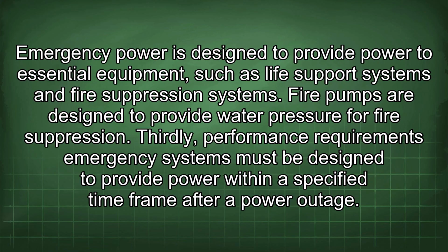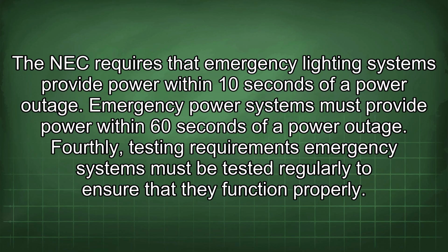Thirdly, performance requirements. Emergency systems must be designed to provide power within a specified time frame after a power outage. The NEC requires that emergency lighting systems provide power within 10 seconds of a power outage. Emergency power systems must provide power within 60 seconds of a power outage.